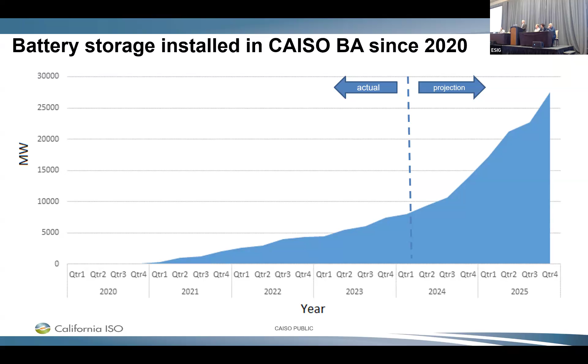The batteries are coming fast, and now that they're hitting the grid we're learning more about how to manage them. At first it was a little hairy. With such a large battery installation, they've displaced our traditional resources that supplied our regulating reserve. We used to have a lot of hydro and combined cycle plants providing our regulating fleet, and now 90% of it is battery providing our AGC regulation units. They respond very well, faster than hydro even. We actually have to program our AGC system to slow them down because they move faster than the rest of the fleet on the grid. They really have increased our reliability and stability.